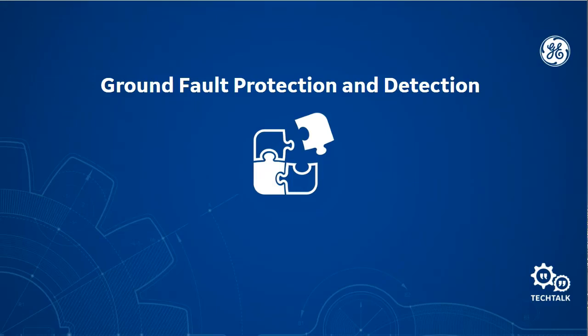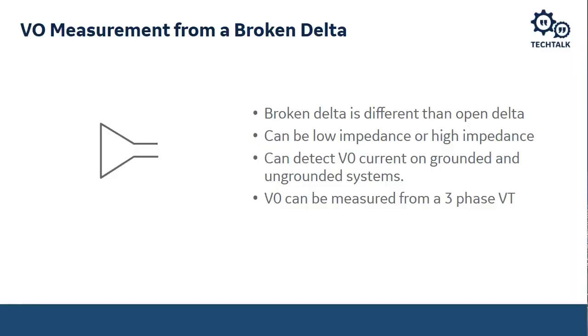So let's talk briefly about ground fault protection and detection, specifically on low impedance and high impedance systems. As I mentioned, on ungrounded and high impedance systems there is no ground fault current, or very limited ground fault current, which is not going to be detectable. So how do we detect a ground fault if we're not going to have enough current available for high impedance and ungrounded systems? The alternative is to use voltage, because that's the only other measurement we have in our power system, and specifically a zero sequence voltage, or what we refer to as a broken delta.